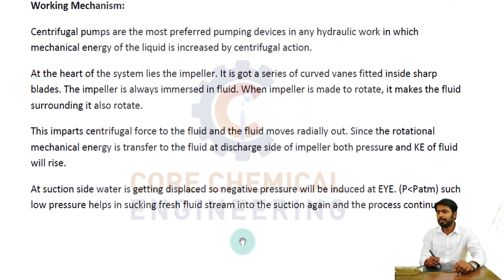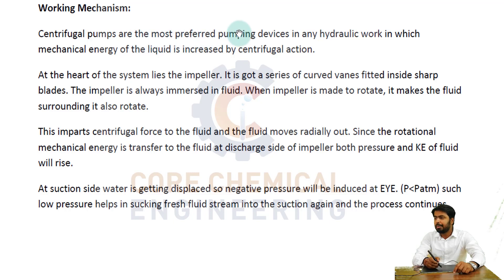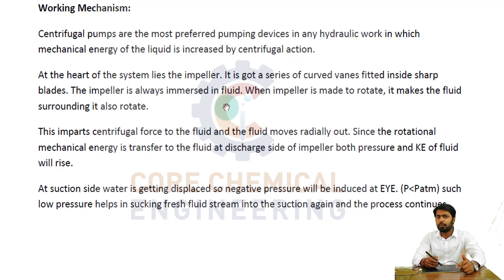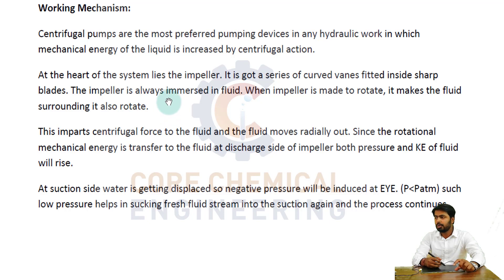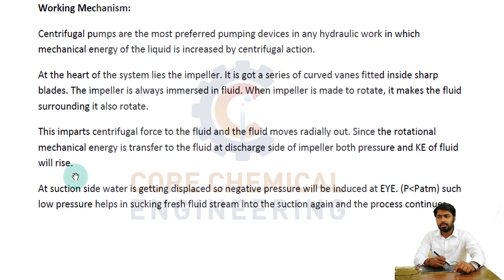Now let's discuss the working mechanism. Centrifugal pumps are the most preferred pumping devices in hydraulic work, in which the mechanical energy of the liquid is increased by centrifugal action. At the heart of the system lies the impeller, which has a series of curved vanes fitted inside the shaft blade. The impeller is always immersed in fluid. When the impeller is made to rotate, it makes the fluid surrounding it also rotate, which imparts centrifugal force to the fluid, and the fluid moves radially outward. The rotational mechanical energy is transferred to the fluid at the discharge side of the impeller, so both pressure and kinetic energy of the fluid rise.